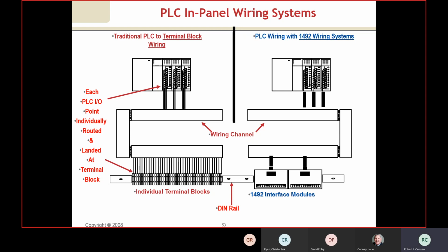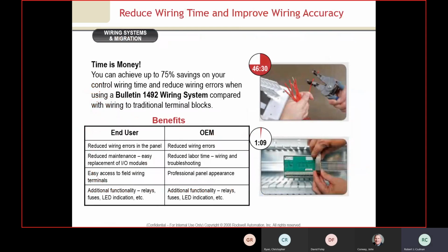Instead of routing each wire individually on the left-hand side to the terminal blocks below, you'll notice on the right-hand side it's one big wire that goes through to the interfacing module. This looks like it's not true, but it is - you look at the time it takes to strip the wires, cut the wires, put them in by hand and screw them in, versus the time if you're using this system. You'll notice 46 minutes at the top and a minute at the bottom, because essentially all you're doing is snapping that onto the DIN rail and snapping the connector wire on the right, wiring that all the way to the unit on top. Very, very fast.